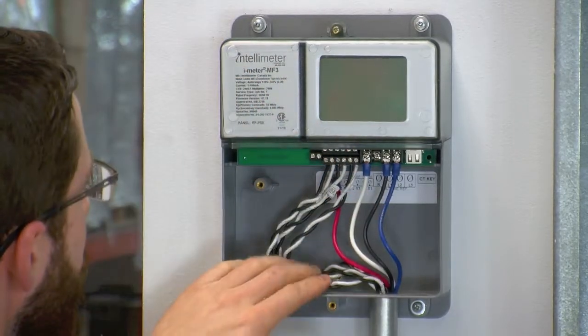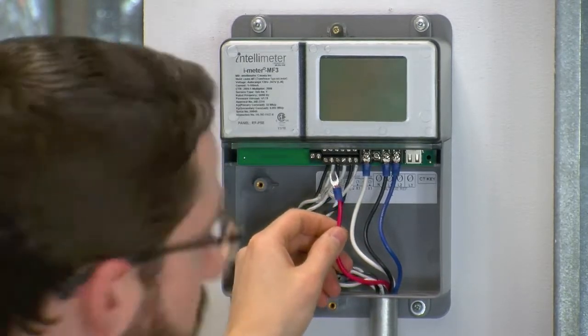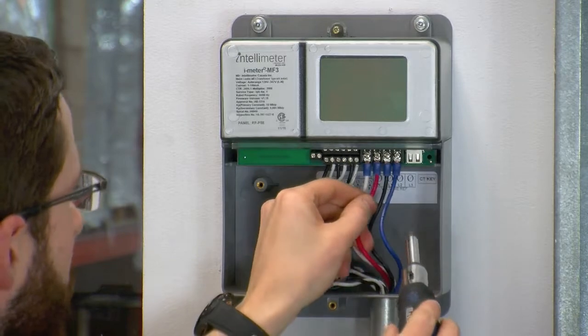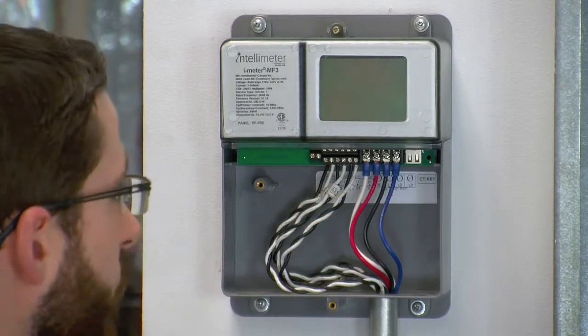Now for the reference voltage, we use fork connectors. Loosen off the terminal screws, but be careful not to loosen them too much as they can easily fall out. And terminate your neutral, line 1, line 2, and line 3 wires.